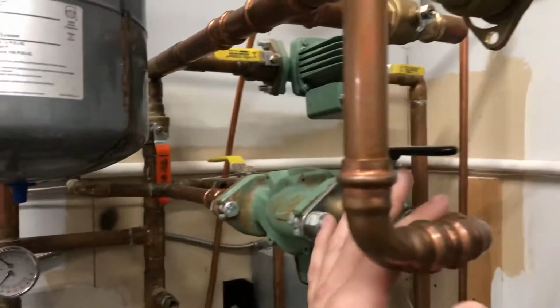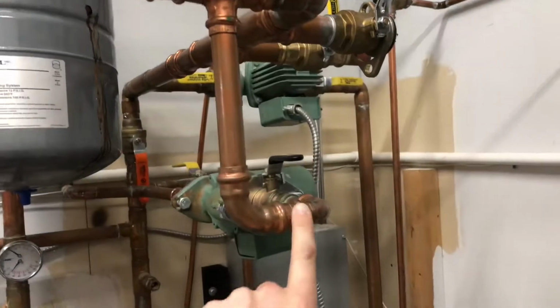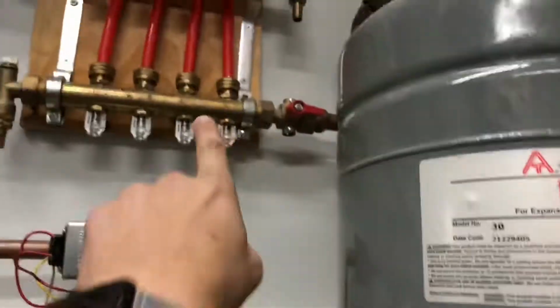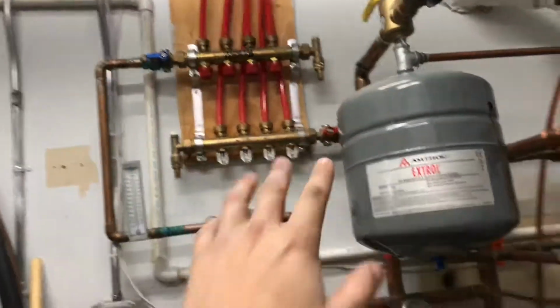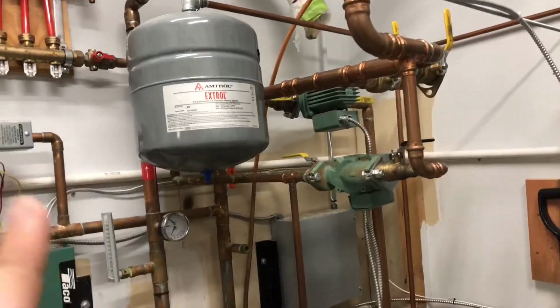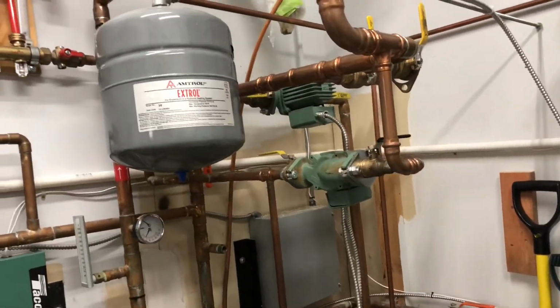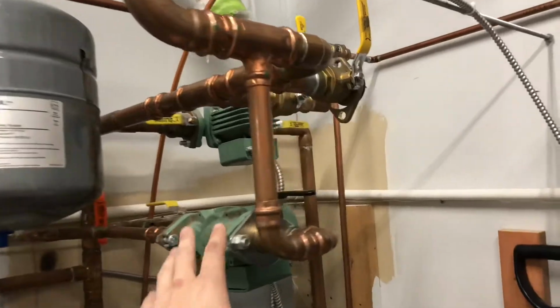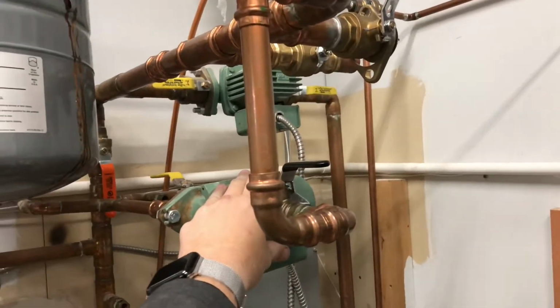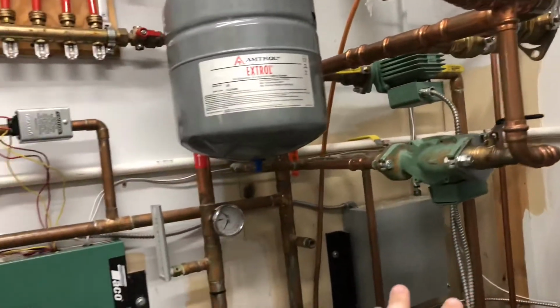And then here's our zone 2 circ pump. So it comes off the main feed, goes here, goes up, and supplies for upstairs. So once you have all of the water flowing where you want it, and again, as long as these pumps are after you tee the hot water, you're fine. Just make sure that they're on the right one.